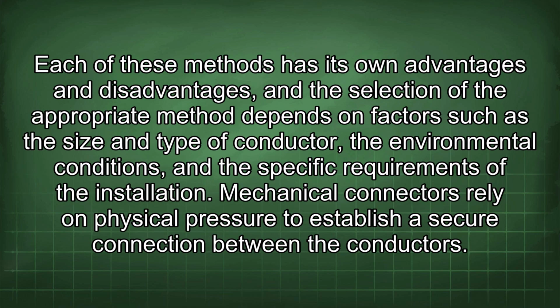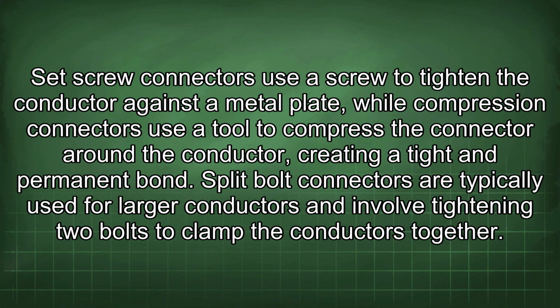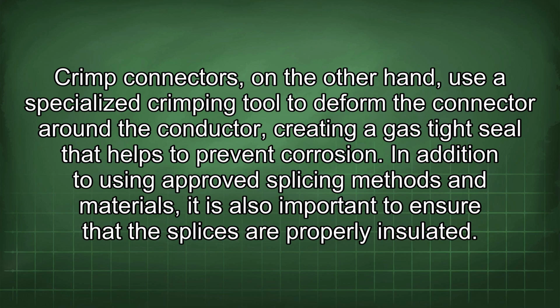Each of these methods has its own advantages and disadvantages, and the selection of the appropriate method depends on factors such as the size and type of conductor, the environmental conditions, and the specific requirements of the installation. Mechanical connectors rely on physical pressure to establish a secure connection between the conductors. Set screw connectors use a screw to tighten the conductor against a metal plate, while compression connectors use a tool to compress the connector around the conductor, creating a tight and permanent bond. Split bolt connectors are typically used for larger conductors and involve tightening two bolts to clamp the conductors together. Crimp connectors, on the other hand, use a specialized crimping tool to deform the connector around the conductor, creating a gas-tight seal that helps to prevent corrosion.